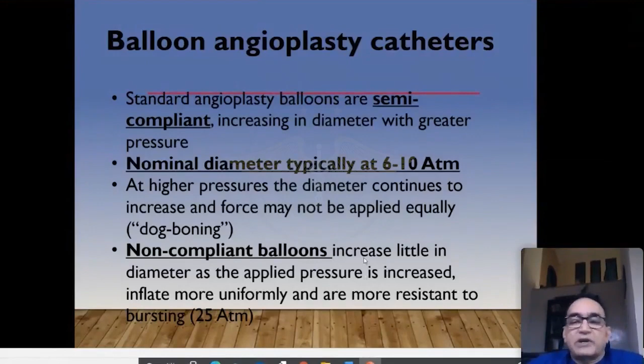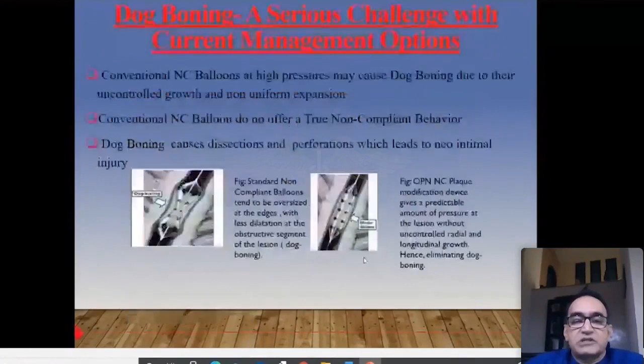The non-compliant balloons are called non-compliant balloons, but actually they are also not really non-compliant. They are kind of less compliant balloons, but they are not as compliant as semi-compliant balloons. Even they increase slightly in their diameter when you go to higher pressures. That is the reason why people have come out with better and better balloons. The non-compliant balloons increase relatively less in diameter as the pressure is increased, but the conventional NC balloons, at high pressures, may cause dog boning also due to their uncontrolled growth, and conventional NC balloons do not offer a true non-compliant behavior.